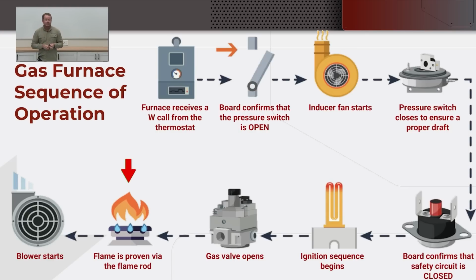So when you run into gas pool heaters, for example, and all of a sudden it's going through this whole sequence, it's trying to prove flame. You see flame, but then it shuts off again. So it goes through all this and then it shuts off again. That's almost always because of an issue with this flame proving, and a lot of times it's because of grounding, because the whole thing is a corroded mess and nothing's grounded the way it's supposed to be anymore.